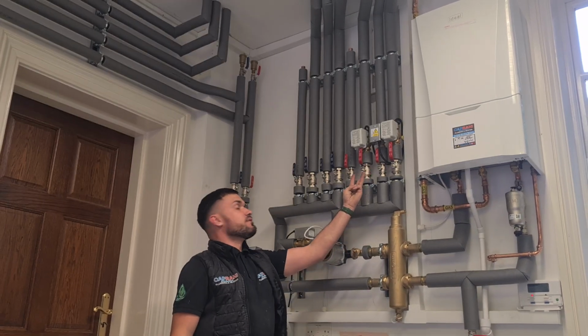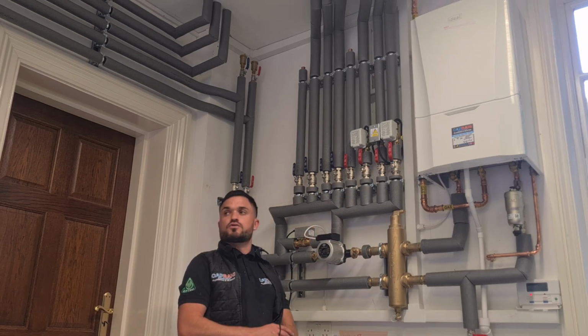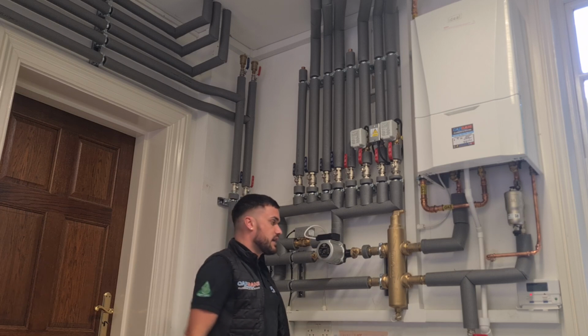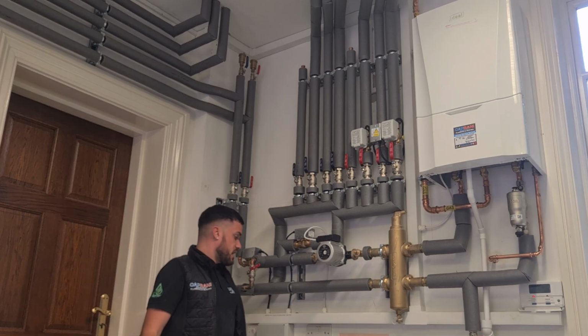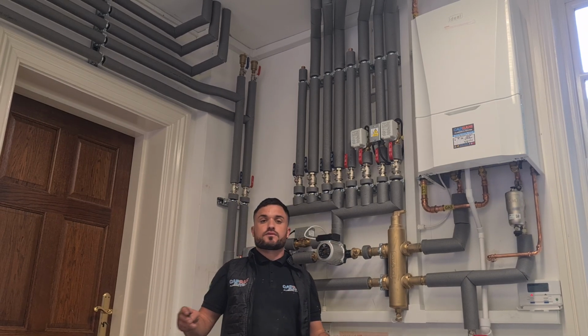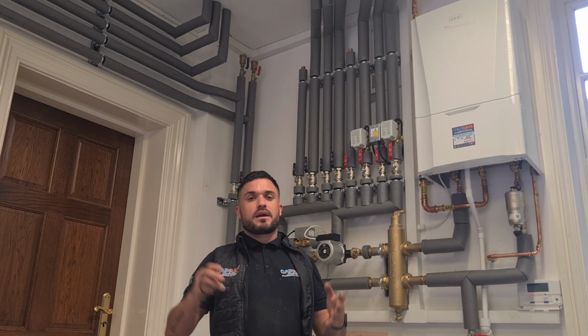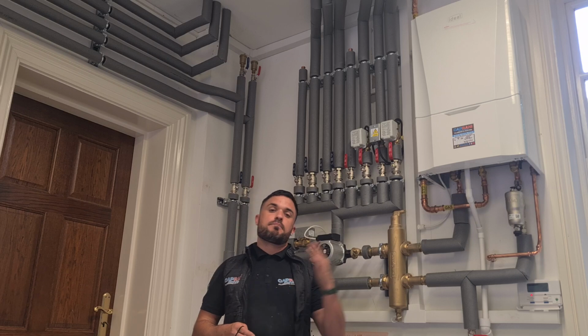We've incorporated 3 zone valves here as well. We have an upstairs kitchen and a downstairs manifold. This house runs fully off underfloor heating. So again, it's a pretty simple system, all right into a consumer box here, with a switched fused spur for local isolation. We've upgraded all the stats throughout the property, as well as the wiring manifolds at the underfloor heating, because the old ones did not accommodate a switched live back to the boiler.